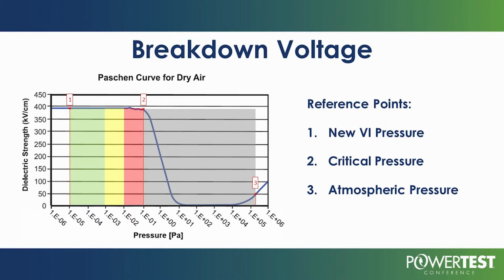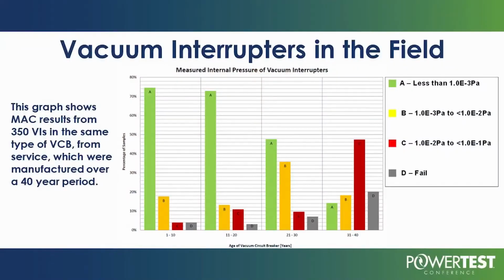As its life goes along, there is a bathtub failure curve with every device, with everything, even with people. As that time approaches, they begin to fail. When they begin to fail, you need to have a plan to either replace them, replace the switchgear, replace the breakers, or to condition the interrupters so they will live in service and operate properly for many more years. And that's what this paper is about, that process. This is a study that was done of about 300 plus vacuum interrupters and similar circuit breakers that all were in service for a varying length of time.